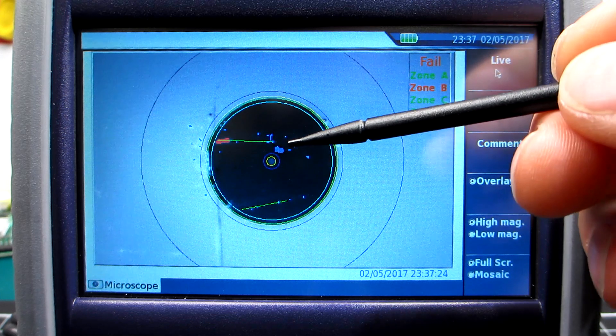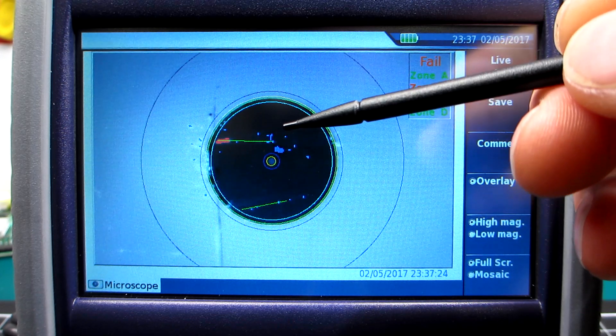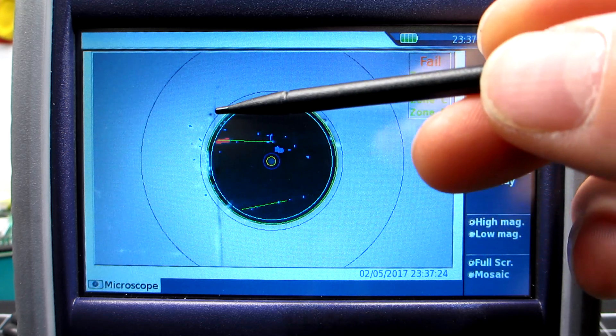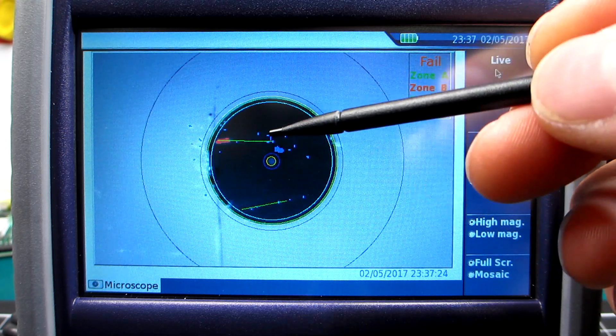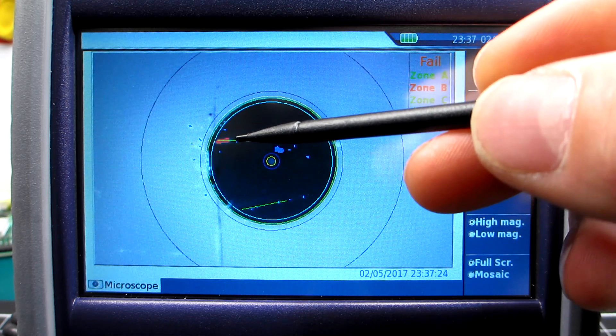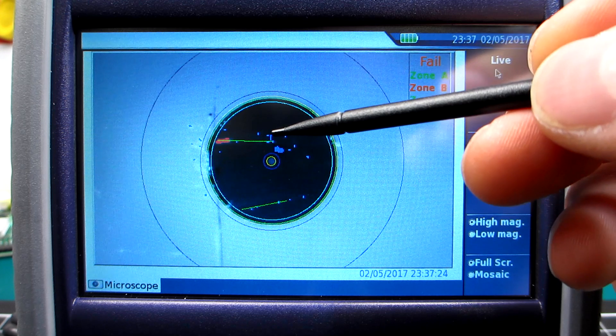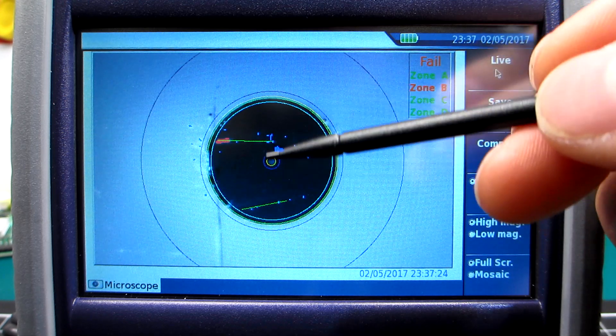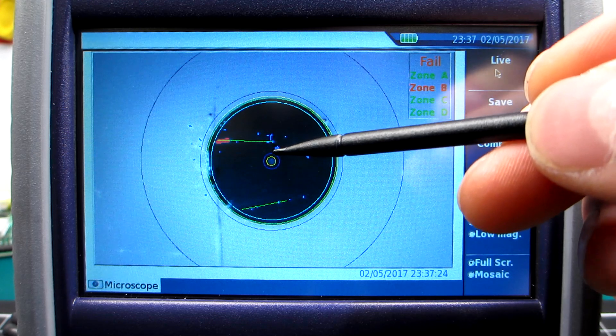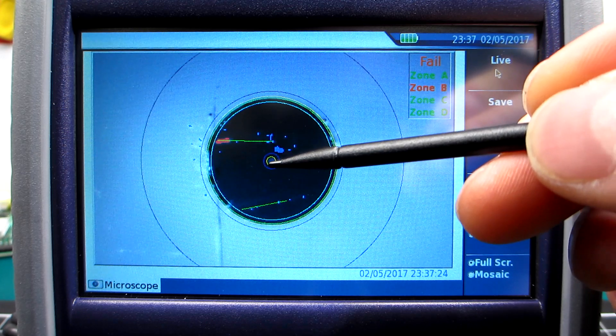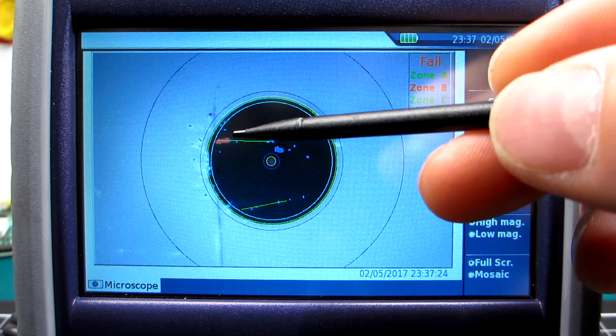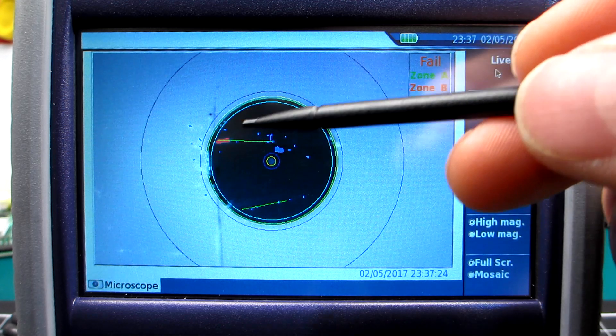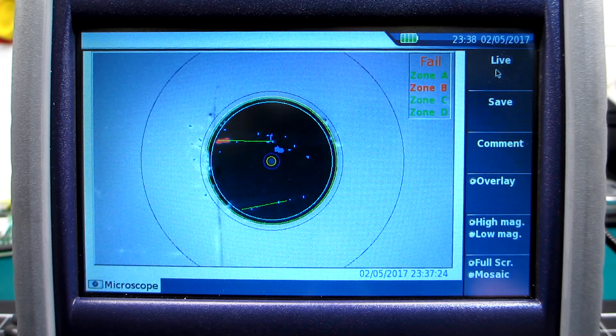Bang. You can see there's the blue sections, the blue dots. You got the dirt it's found. You got these green lines. It's found the scrapes. But they're not causing too much of a problem. It's failed only on one chunk just over here. So if there are a few scrapes sometimes it passes it. It depends where it is. If that scrape went through that central piece there, the little yellow circle, definitely a fail. If there's anything in there that's where your main light path is. But even if it's out here it can cause like reflections and stuff and then that's going to interfere with your signal. So let's give that a bit of a clean and see what happens.